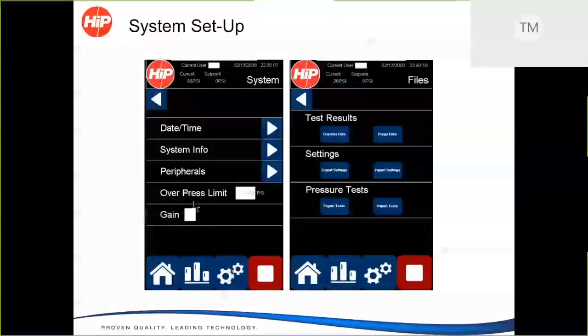Gain is also a very important variable because that controls how fast the system runs. So you see it all the time: everybody wants to run a pressure test as fast as they can. But depending on how much volume is contained inside the unit that you're testing, you might be able to build that pressure really fast, or it might take a long time. If you were testing a very small piece of piping with a gauge on it and you wanted to do a gauge test, you're going to have a very small amount of volume where you can build up pressure really fast on your pneumatic pump. But if you're testing a large valve that maybe has an internal volume of 4 or 5 gallons, it's going to take a long time for that pump to run and build that pressure up.